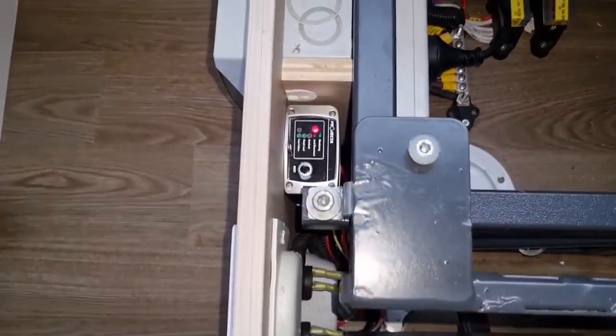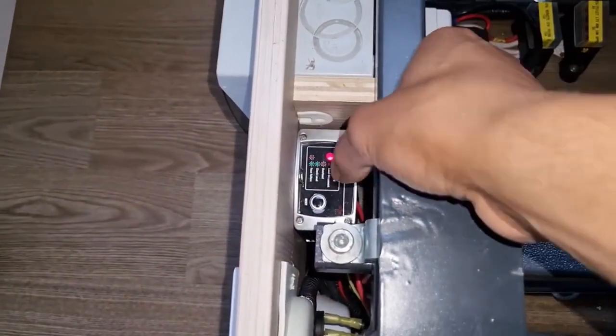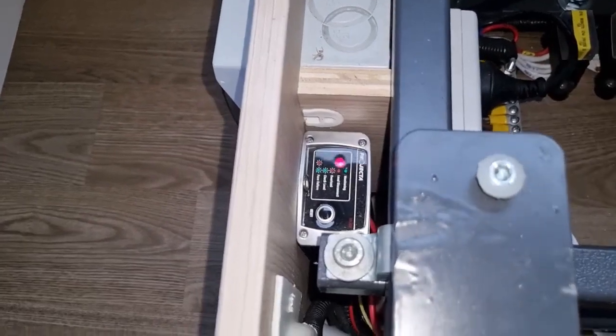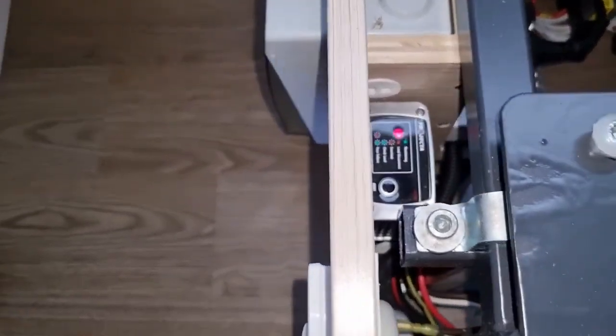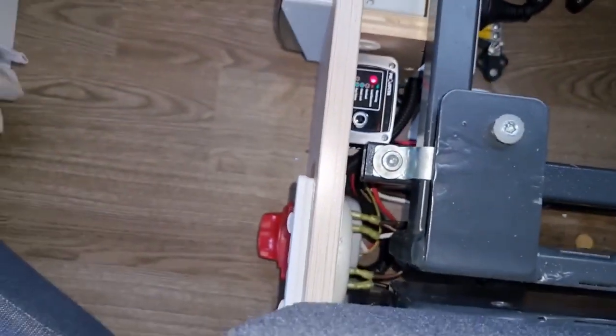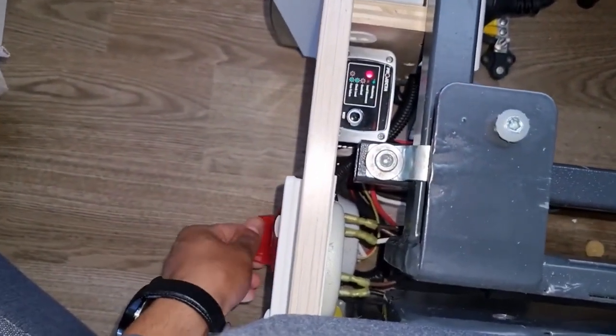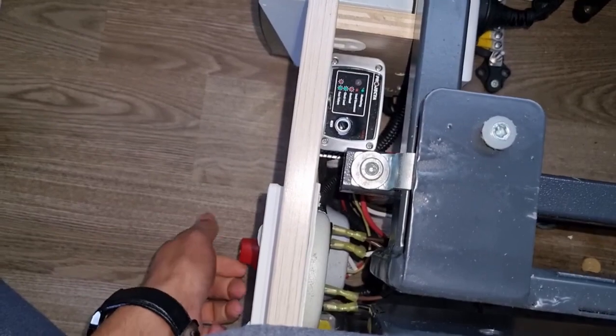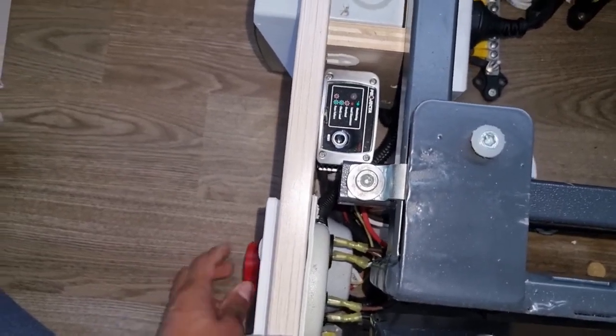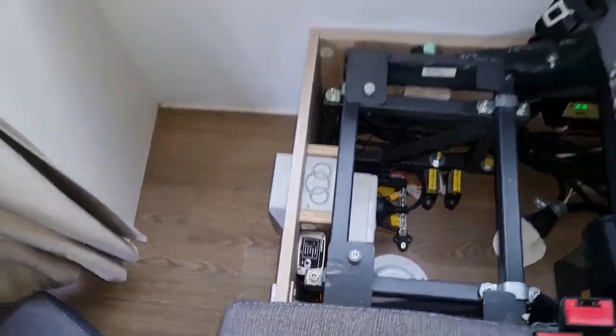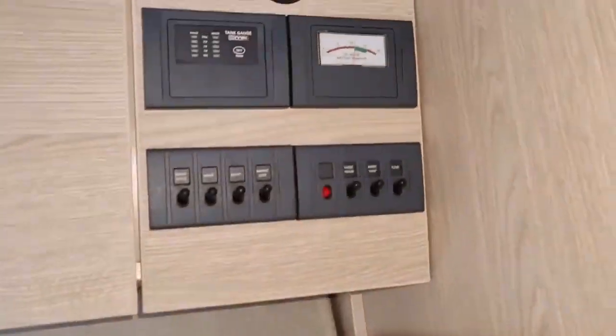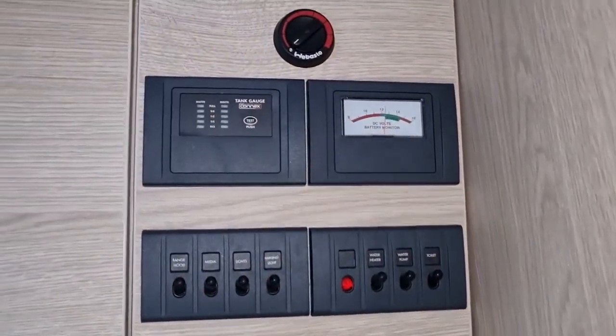Again, we're here at the low voltage disconnect, which has cut off the battery. As you can see, it's turned off here. So again, come to the front, make sure all your loads are off. I'll try and show you both at the same time. I'll come here to the isolator switch, turn it off, turn it back on, and the voltage is above 12, so it won't cut off again.